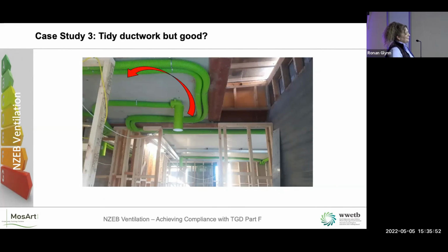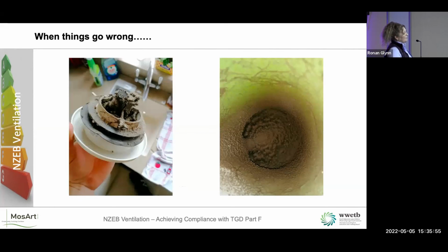This is another example. This is the extract to an MVHR unit. It's been running for 9 years like that. The ducting was never cleaned, probably no anti-static ducting. So you want to get anti-static, antimicrobial, so the dirt can't build up on it and germs and stuff can't live on it either. So the MVHR unit and manifolds were inside the thermal envelope and accessible, so cleaning was possible. The homeowner was great for changing the filters, but they just didn't understand beyond the unit. They knew they had to change the filters in this, but didn't understand there's a whole lot of ductwork and stuff going on as well. So the flow rate for that diffuser, as you can expect, is pretty unknown. So I'd say it wasn't great.